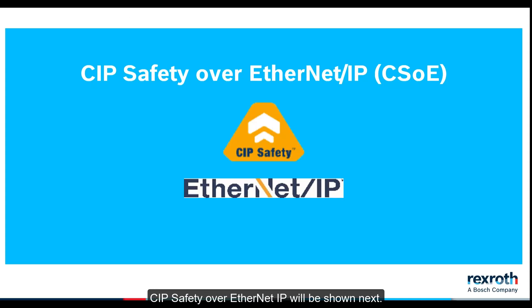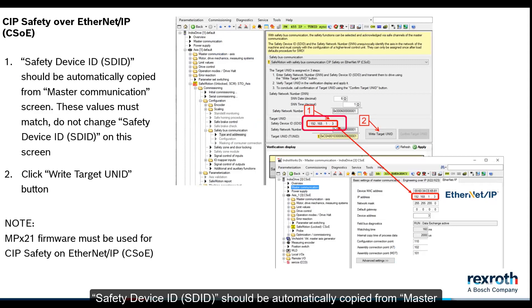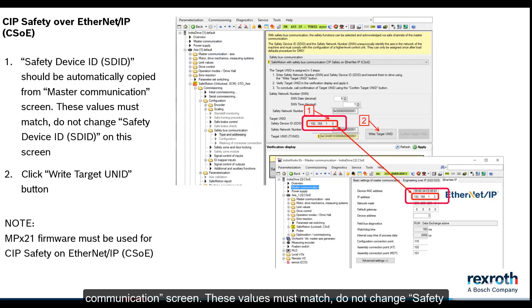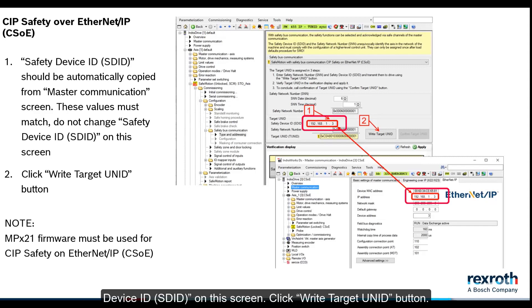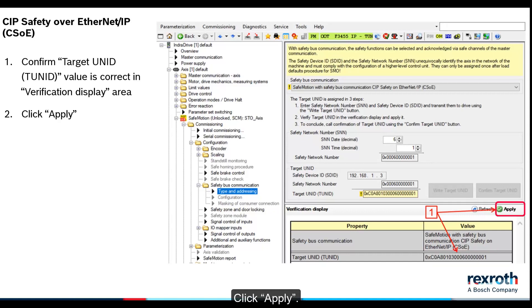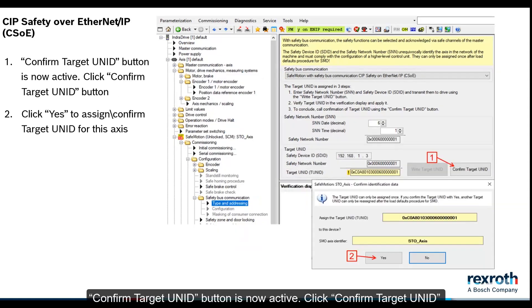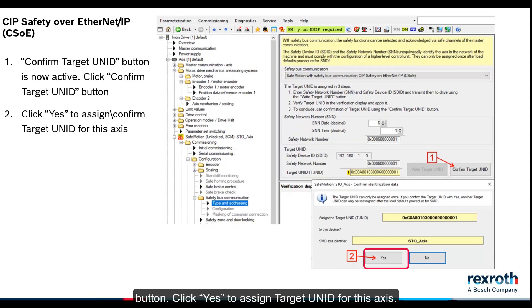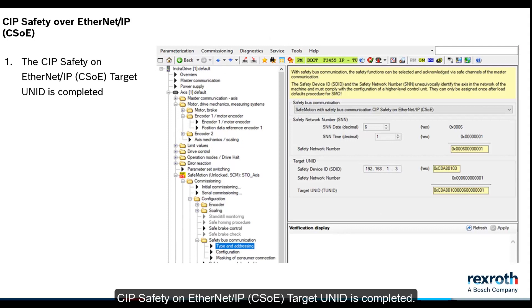CIP Safety over Ethernet IP will be shown next. The safety device ID SDID should be automatically copied from the master communication screen. These values must match. Do not change the safety device ID SDID on this screen. Click write target UNID button. Confirm target UNID value is correct in the verification display area, click apply. Confirm target UNID button is now active. Click confirm target UNID button. Click yes to assign target UNID for this axis. CIP Safety on Ethernet IP target UNID is completed.